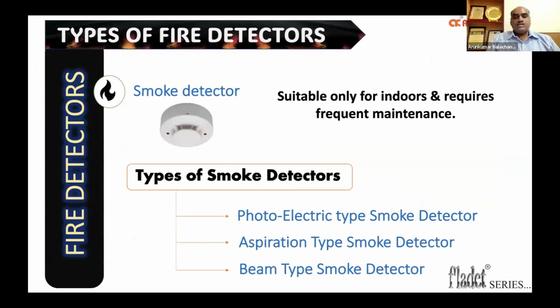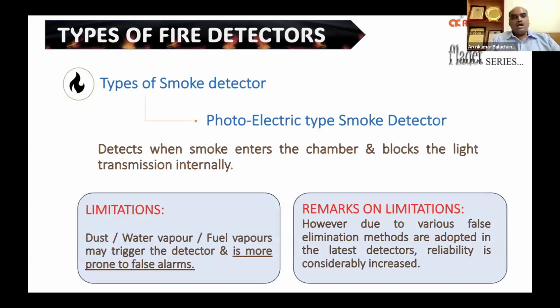The smoke detectors are mainly used in indoor applications. The major types of smoke detectors are photoelectric type, aspiration type, and beam type smoke detectors. The photoelectric type smoke detector is very widely used in many applications, and this is the most commonly used detector. But as I said before, these detectors are mostly used for indoor applications. Whenever there is dust, water vapor, or fuel vapor, it may trigger and give a false alarm. However, I would like to highlight that in newer technology detectors, due to various false alarm elimination methods being adopted, the reliability of these detectors is considerably increasing day by day.